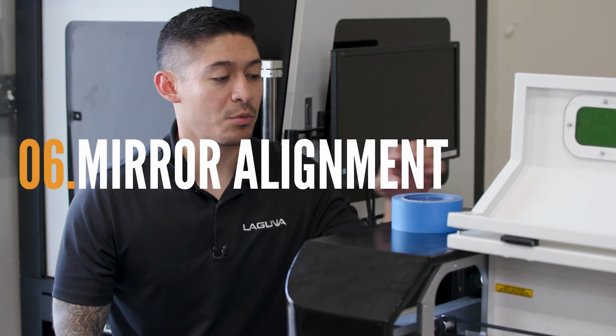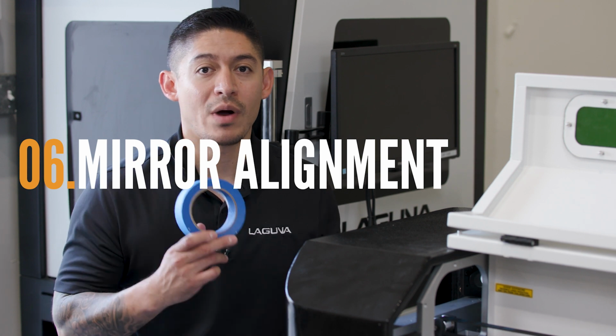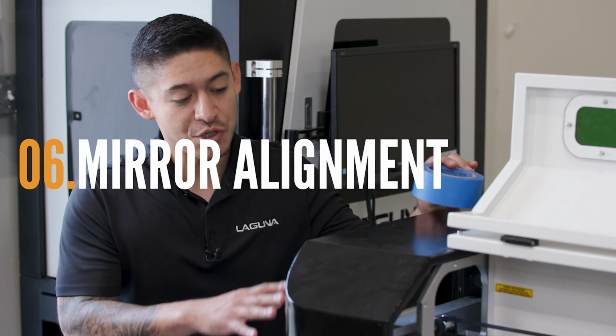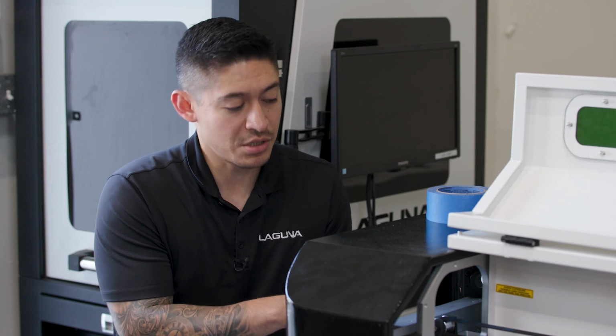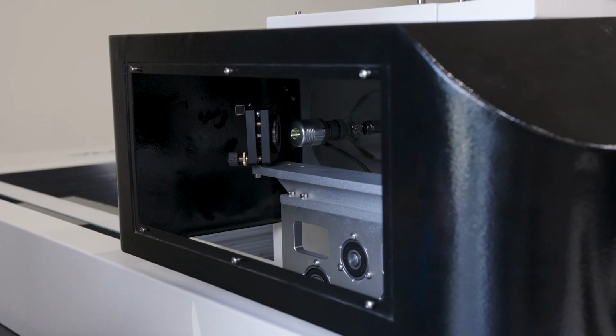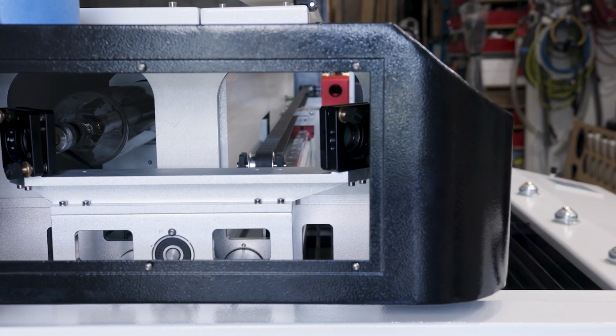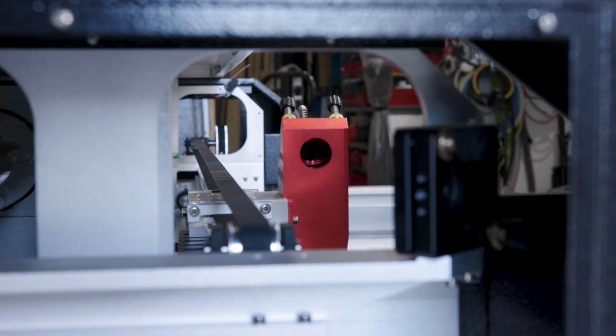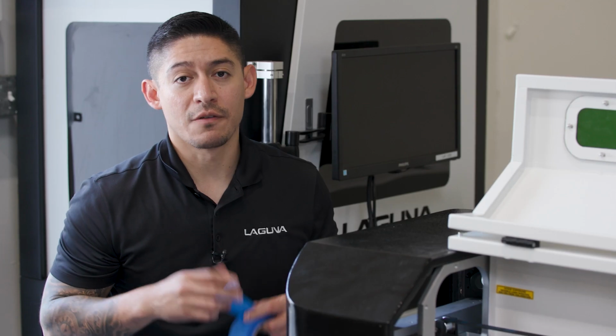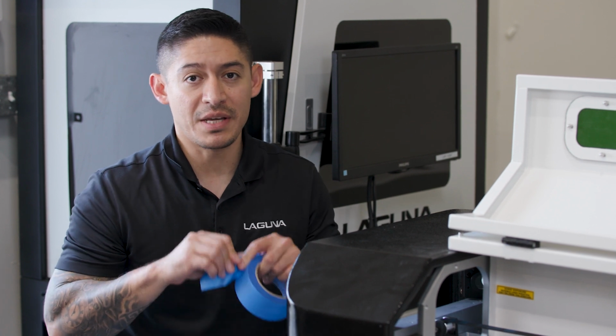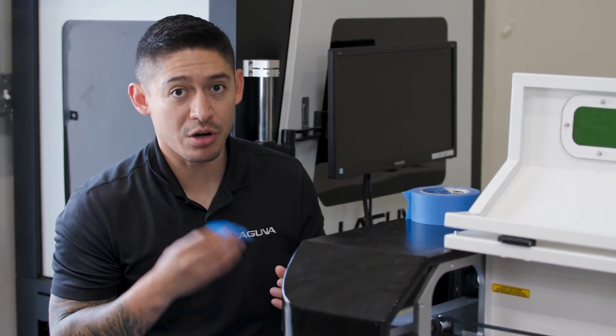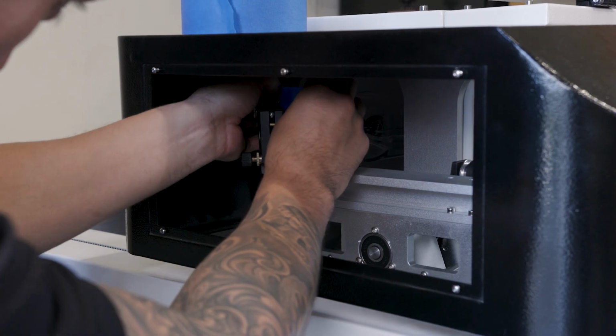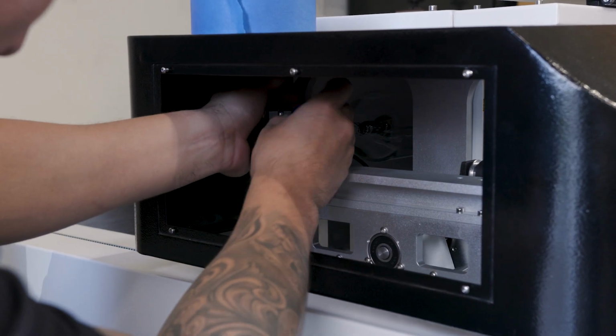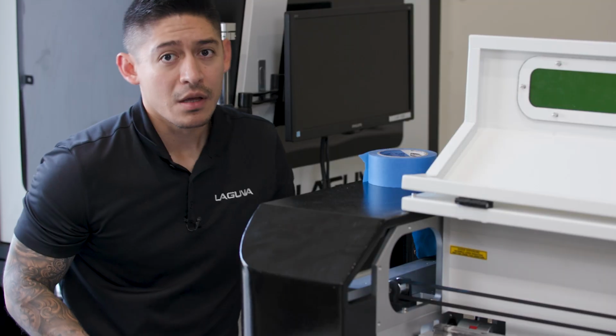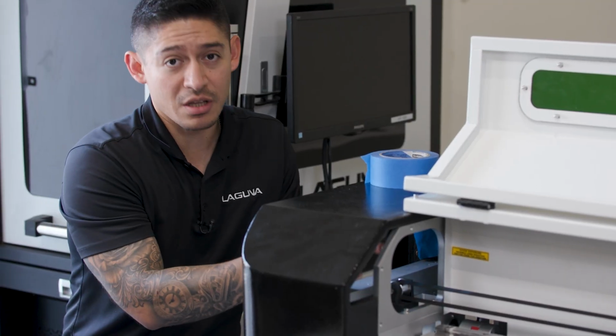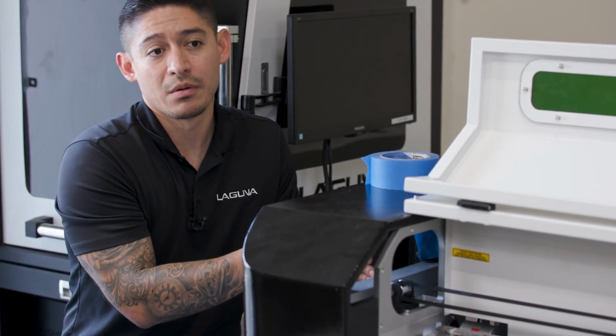Okay, so the final step would be to do the mirror alignment. You're going to require masking tape. On this machine, you have 3 mirrors. You have your front mirror, mirror number 1, back mirror, mirror number 2, and mirror coming into the laser head, which is mirror number 3. So the first thing you're going to want to do is cut a piece of masking tape and put it over the first mirror. Then we're going to want to go pulse to make sure that the beam is hitting center point.